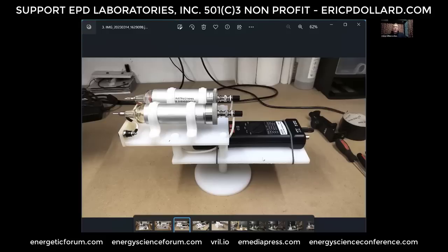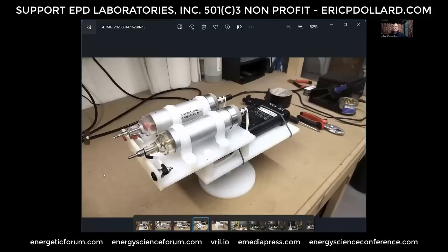It's largely HDPE constructed — there's another shot of it. Those silver high voltage probes actually come out of a Tektronix P6015, which is a 40 kilovolt high frequency probe. So this is good to about 65 kilovolts, up to about 20 megacycles.